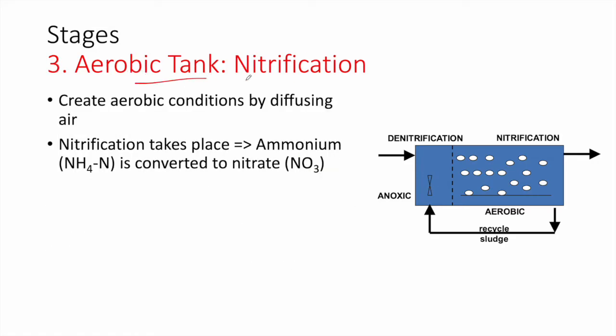Next, in the aerobic tank, we have nitrification. Here we create aerobic conditions by diffusing air using air diffusers and air blowers. Notice there is a lot of mechanical equipment in an MBR wastewater treatment plant. During nitrification, ammonium is converted into nitrate. You might ask: we already removed the nitrate in the anoxic stage, and now we have formation of nitrate again — this is why we recirculate some of the water back into the anoxic tank to remove it.